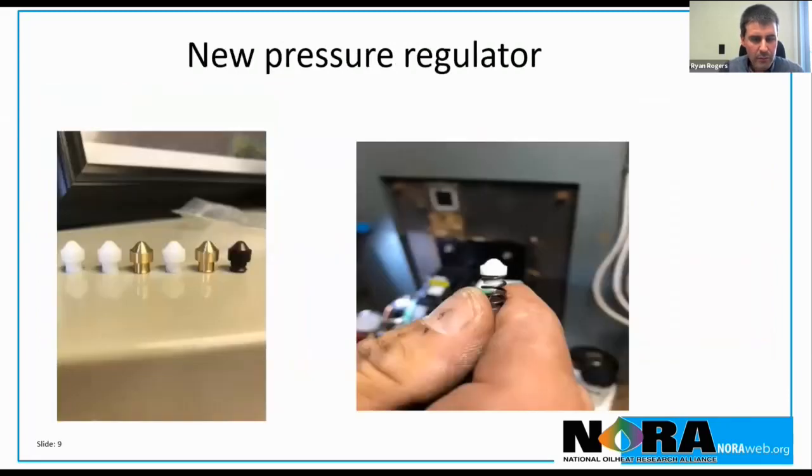So one of the main issues with the pump that we had was the pressure regulator. In the picture on the left, the furthest right is what the Beckett Danfoss comes with, that pressure regulator, and you can see the Teflon and brass pieces that a friend of mine machined. That little piece of nitrile would swell and close the oil off, and we'd have a flame failure.